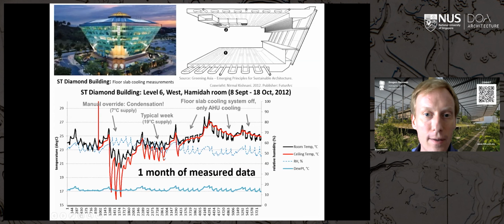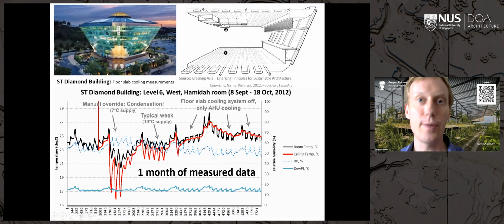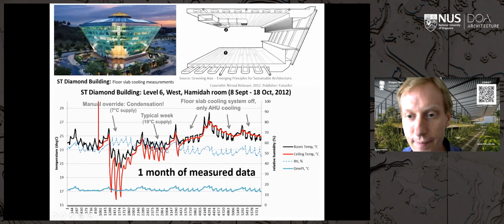So during the correct operation, there's no problem. The ceiling temperature never gets down close to the dew point. But then maybe there were complaints or fear, and it was switched off for the next 3 weeks. You can see once they switched off, the ceiling temperature doesn't drop down every night, and is just allowed to free flow. And therefore, the temperature in the building, the black one is the room temperature, you can see the room temperature also increases because it doesn't get that 40% cooling. 40% of the cooling was basically missing. So these 3 weeks, the temperature was definitely warmer in the building than it should be, because 40% of the cooling system was cut out. So this graph captures all these different types of operation of this slab cooling system. It's quite instructive, and if you just operate it normally, there's no issue with condensation.